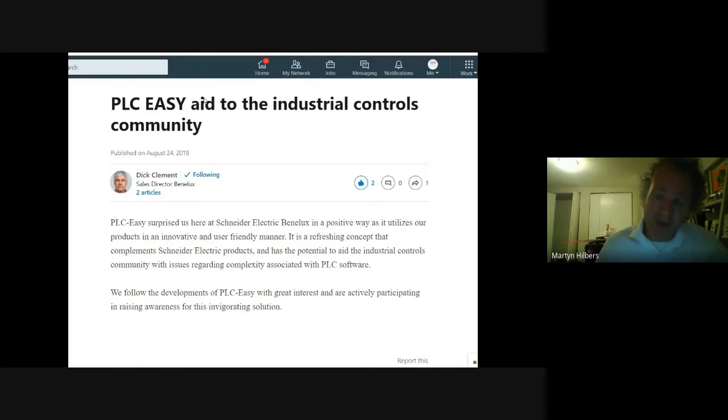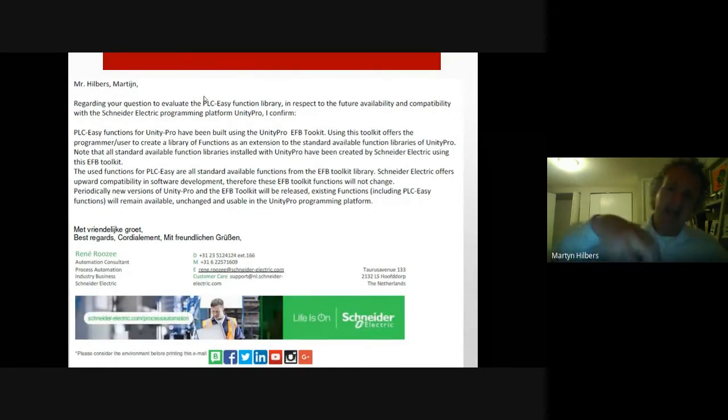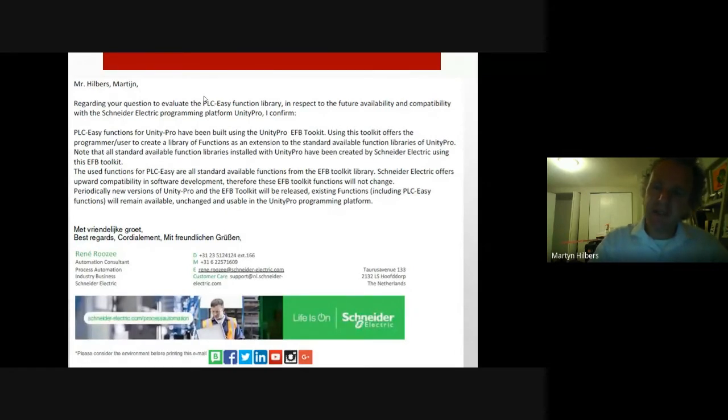Now, there's a couple of testimonies by Schneider and Benelux in Europe. One thing is that they're quite taken in by the solution, but the other thing that they're saying is that this software is written exactly the same way as Schneider does themselves. So it's not written in the IEC 61131, but it's written in C language. And the Schneider company provides a software tool, and they call it the EFB toolkit, which allows you to program in C and import that in an IEC 61131 environment in their EcoStruxure or in their Unity Pro. And so the big advantage of that is that it's much faster. And the great thing is when Schneider upgrades their hardware or their programming environment, this remains supported. So it's supported indefinitely.